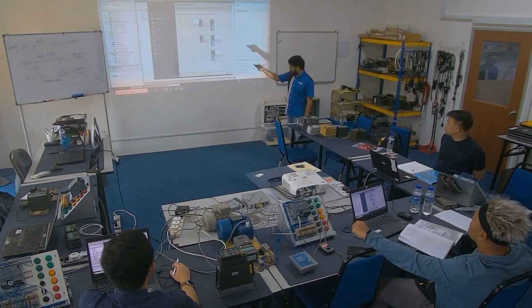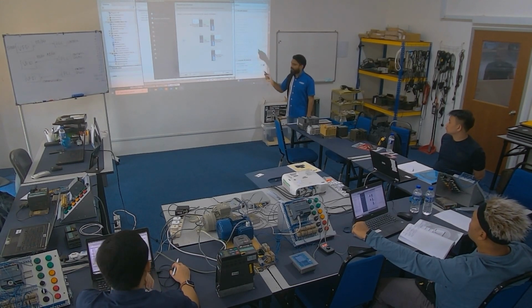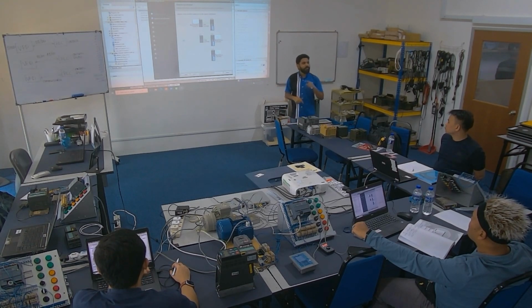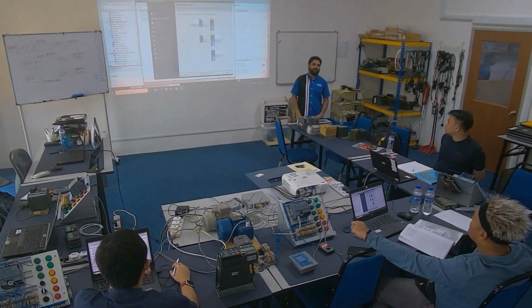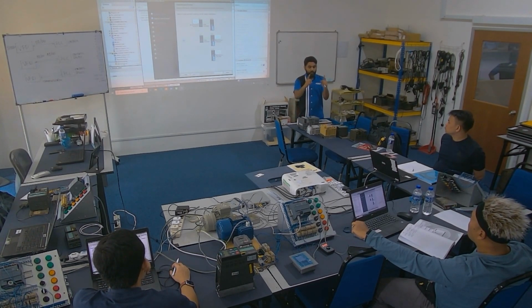Okay, so here inside we do it. But if I choose the first one, in the program I need to do that. So how to do that is, let's say you key 50 Hertz, so it must be within 2 seconds, so you need to use a timer function, put 2 seconds, within 2 seconds it slowly increases until 50. So you need to do an additional program for that.